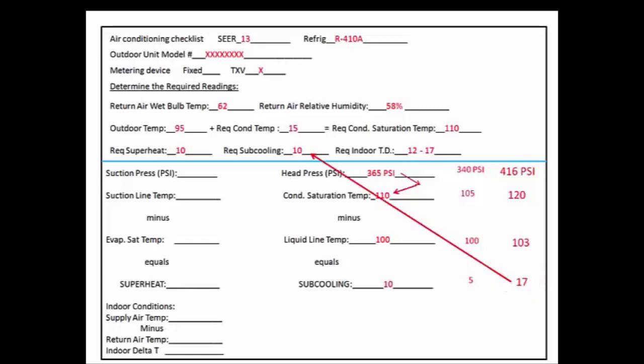Our required subcooling is 10 degrees, so we have high subcooling. So the high head pressure of 416 psi and the high subcooling tells us we have an overcharged system and some refrigerant needs to be taken out.